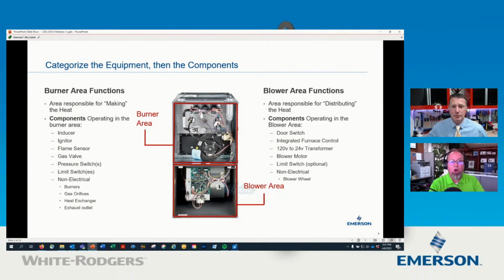Typically you will always find the components listed here in the burner area, and the same with the blower area. So let's look here. How many things do you have to memorize on a gas furnace? Not a lot. Inducer, igniter, flame sensor: those are three 120 volt circuits. Gas valve, pressure switch, limit switch: those are the three that deal with the low voltage. That's it. It's a short list.